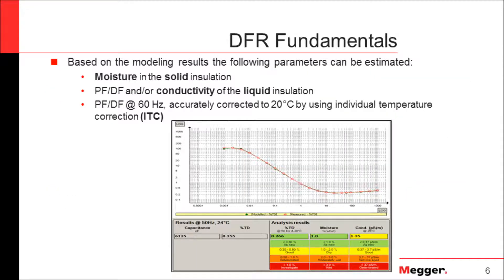What are we trying to do with dielectric frequency response? Fundamentally, we are looking at the moisture concentration in the solid insulation of this complex insulation system in our power transformer. We can also look at the power factor, dissipation factor, and conductivity of the liquid insulation — whether mineral oil, ester oils, or even air if the transformer is without oil.